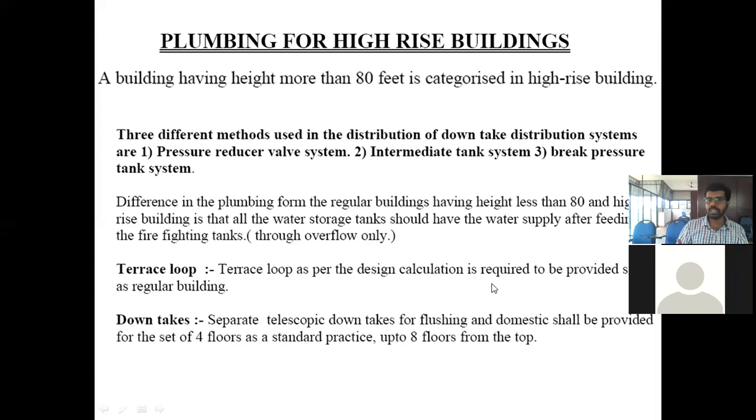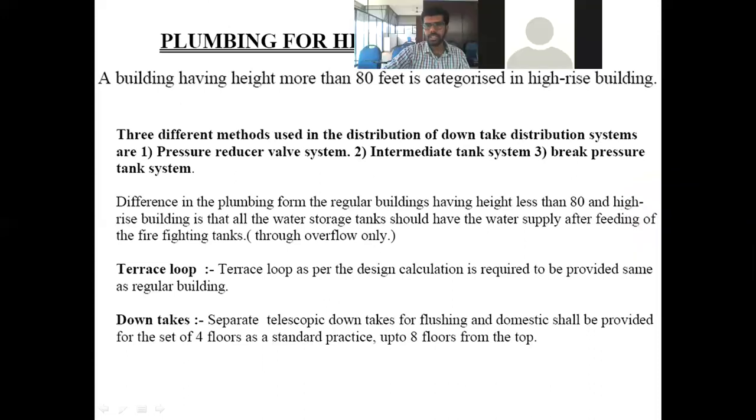Because we need water supply each day, right? So in order to make sure that the water is always present in the firefighting tank, as per the design, we have to store the water inside the firefighting tank initially. Then the overflow from the firefighting tank only will reach the domestic water tank. Okay, so that's what it meant.